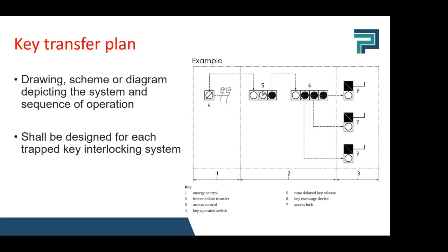The standard also says that a key transfer plan shall be designed for each trapped key interlocking system. And here on the right, you see an example of this key transfer plan. It is basically just a drawing, scheme, or diagram depicting the system and sequence of operation.